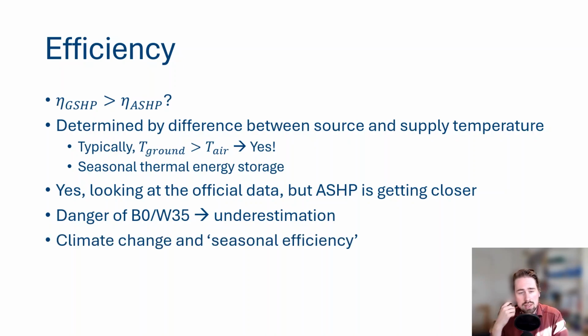But also, and that's the other side, due to climate change, regions that typically had colder winters in the Netherlands, Germany, Belgium are experiencing less and less extreme winters. So it's typically getting warmer outside. And this first point, where the ground temperature is higher than the air temperature, still holds, but less frequently, because the air is getting warmer. So the seasonal efficiency of your air source heat pump, here in practice, is getting closer to, or even sometimes better than, the ground source heat pump.